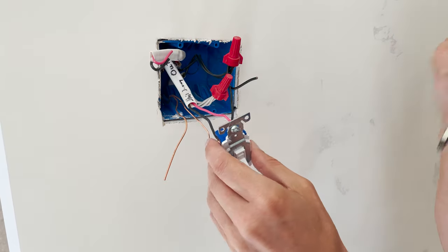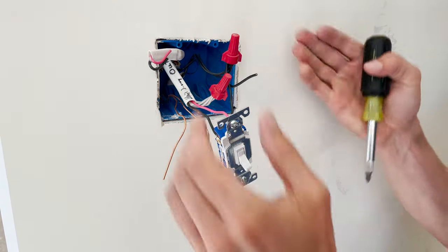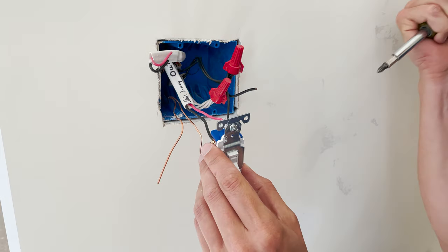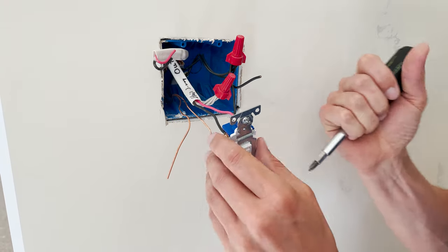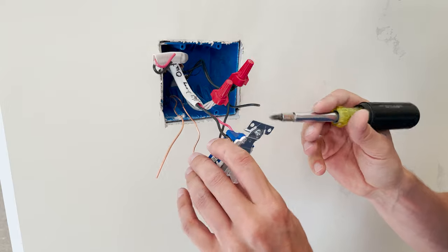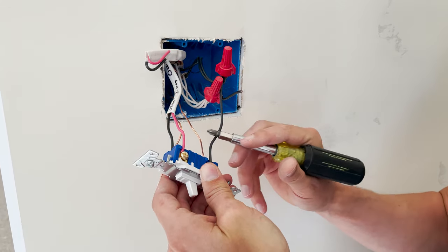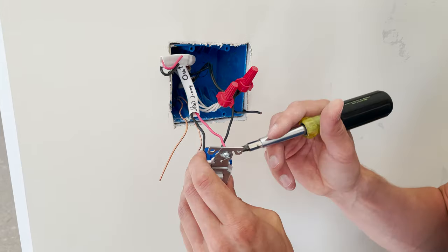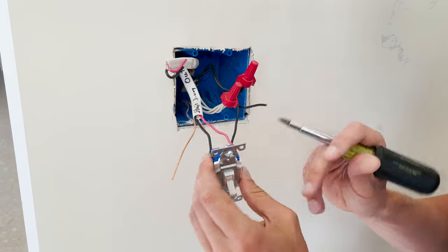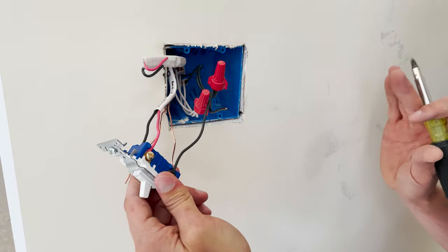So if you go over to the other side, so again, power's coming into this. This is going over to the other three-way switch. The other box, you do the same thing, but instead of having the power in going here, you have the power out to the light going here, and then your two wires are hooked up just like that. Other than that, it's the exact same.